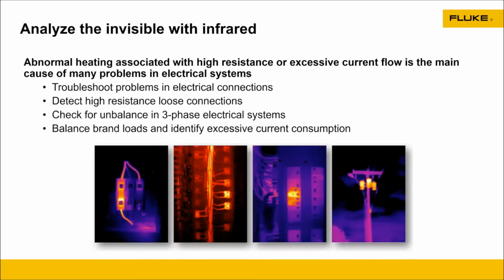Here's some great pictures that we've been able to pull, because it really does help you troubleshoot electrical problems that could potentially cause a fault later, or whatever that may look like. A lot of these are on circuit breakers where you can kind of see some hot current running through it. But even from a distance, you can kind of see on this far right picture some transformers, and they can see what's happening on that and potentially energy or some type of fault that might happen with that. But again, a good way to see if you've got excessive current, those unbalance of your three-phase systems, just a great way to look at that.